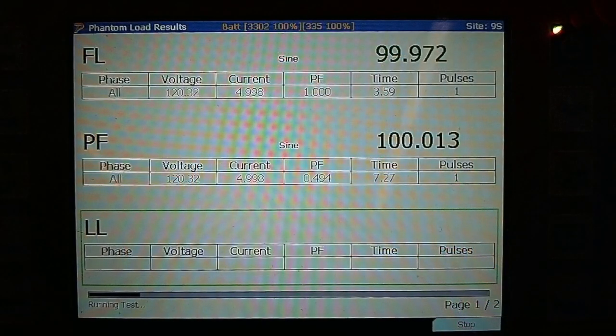Virgil made a comment in the chat room that he does have one meter for solar generation, and it is not bidirectional. He said the solar is connected to the line side of the meter, so at night there is no solar, and he sees a small amount of power going backwards through the meter. So he can only see consumption during the day, when the sun's out. So even on a solar generator, it should be bidirectional, to keep track of the inverter grid sensing power consumed. Yes, I agree with that, Virgil, thank you. And John Young, yes, you are correct.